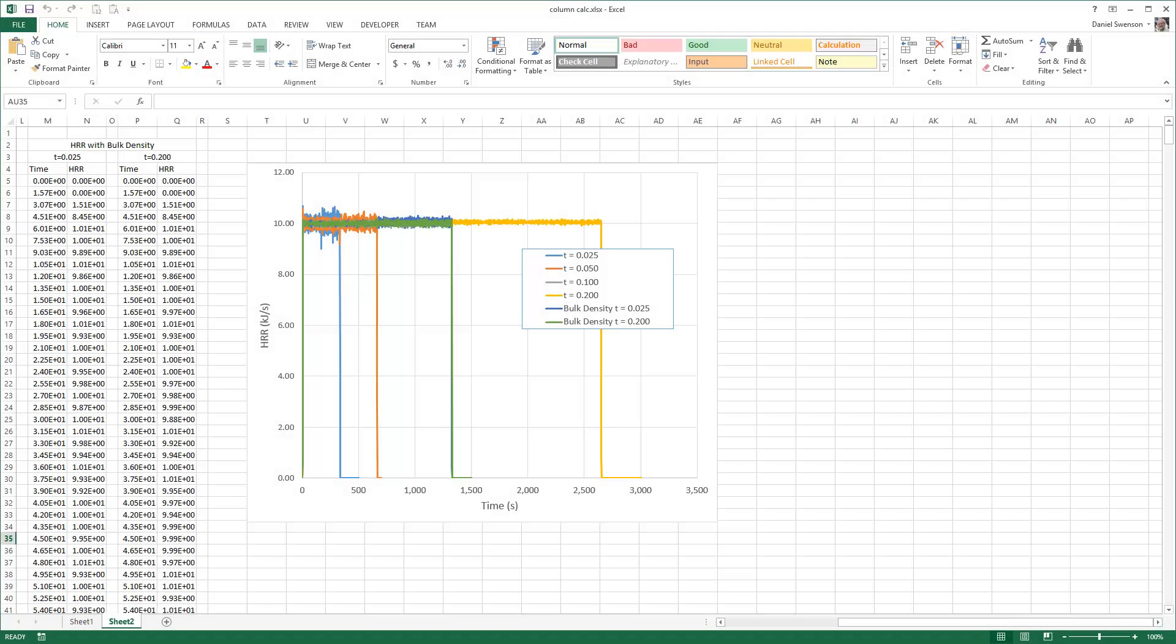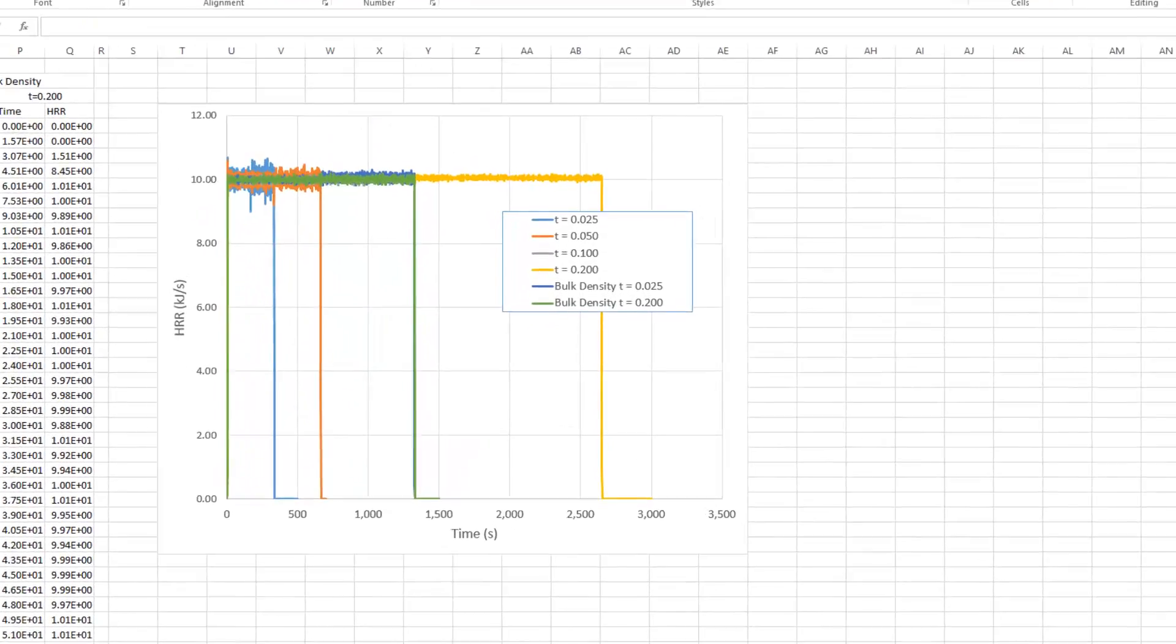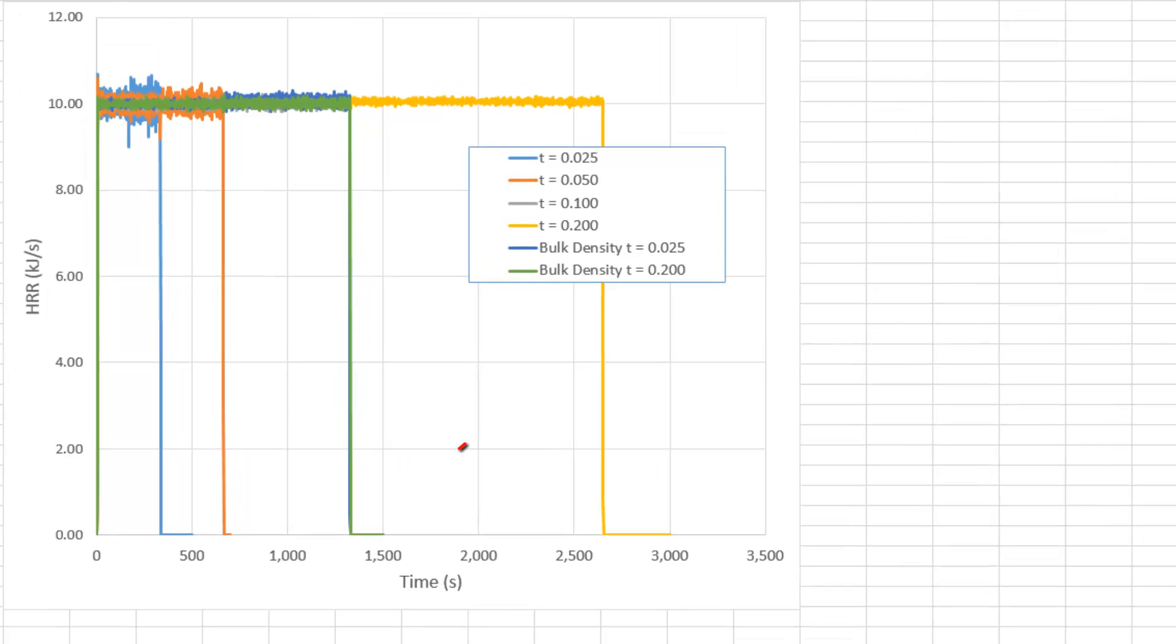That is the result that we see on this plot of the column heat release rate. This figure also illustrates a potential source of error when using burn away. If you do not specify a bulk density, the amount of fuel will be calculated based on the thickness of the surface.